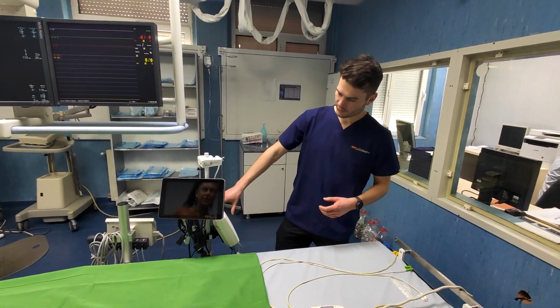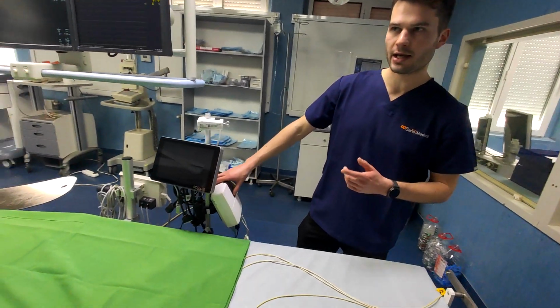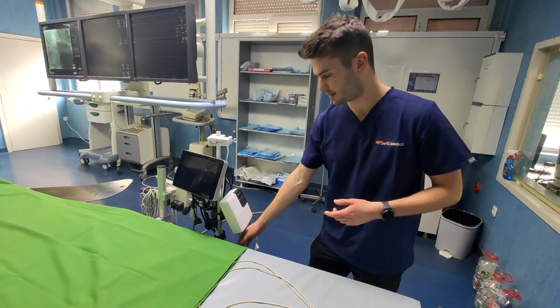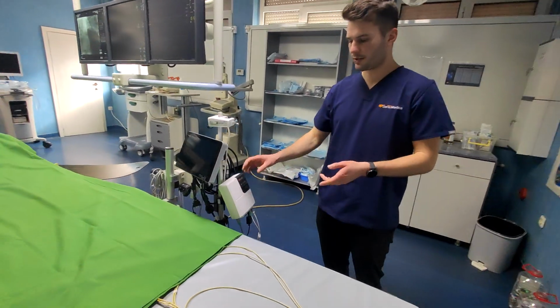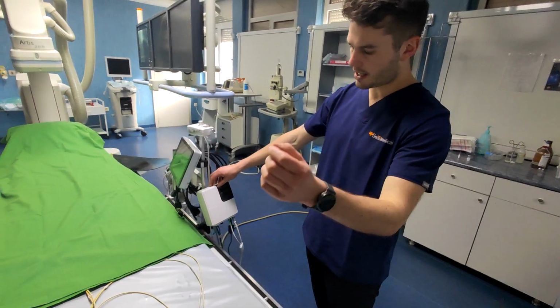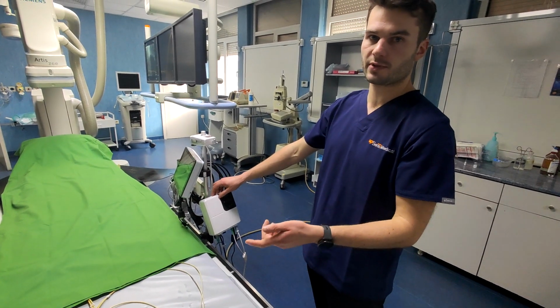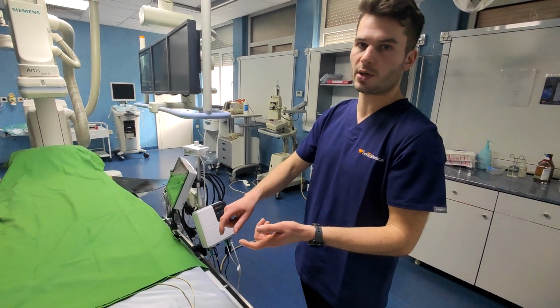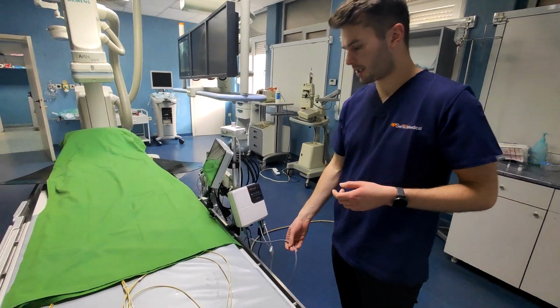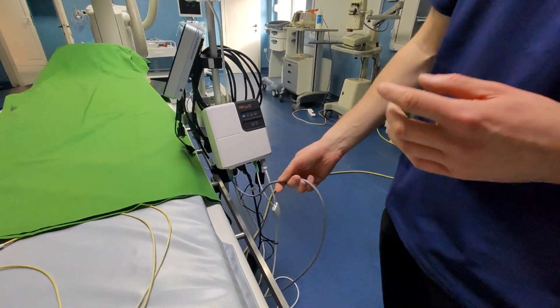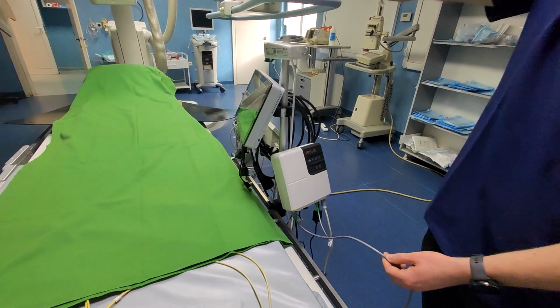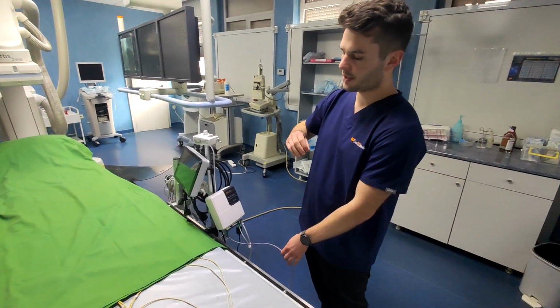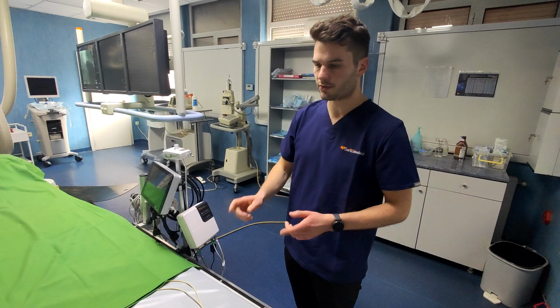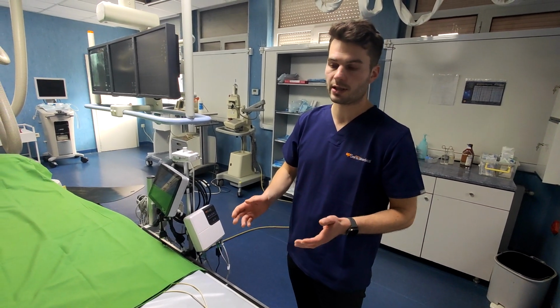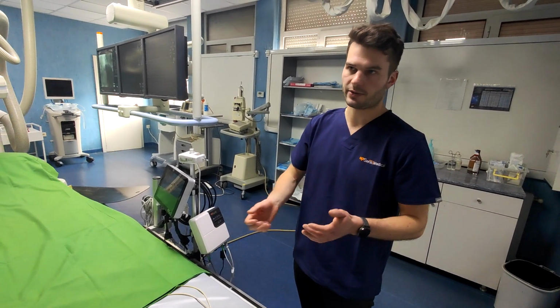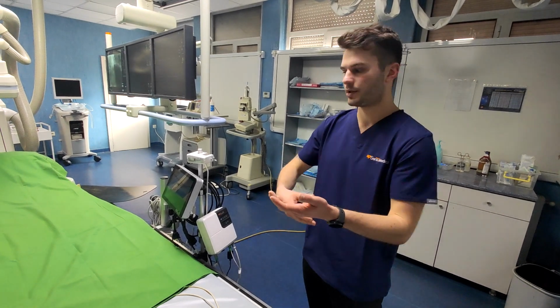So, with this sensor, we've set up an aux or the analog input. The way that this works is it takes the aortic signal from the analog port of the HEMO box. So you only need one cable from the HEMO box after you've set up, and the other signal comes from the wire itself. So it's really tidy. Generally, you find that a lot of sensors don't use their analog port, so it's free.